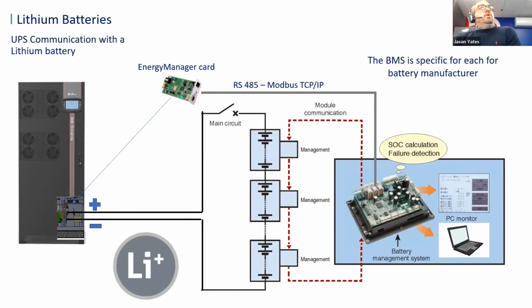Touching on the UPS communication with the lithium system, this is about the BMS specific communication protocol. You can buy a lithium battery system which you can connect directly onto a UPS system without any problems, but the problem with that is it's not a fully integrated package. Therefore, we developed a system whereby the UPS system can correctly communicate with the lithium system, because under certain conditions you want the UPS system to stop charging, or charge, or do certain things. It's imperative that the lithium system is fully integrated with the UPS system, not purely for the control of the lithium, but also for the monitoring and the information that the UPS system puts out to the outside world in terms of the autonomy times, the recharge times, and so on and so forth. So it's important to have a fully integrated system.